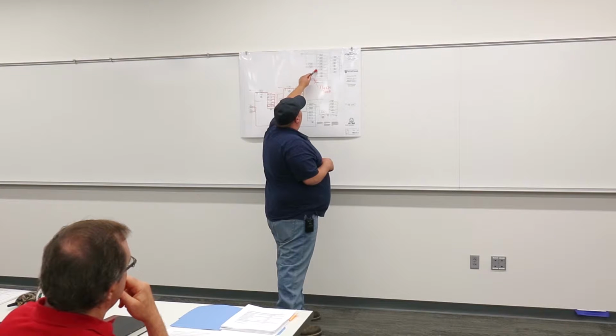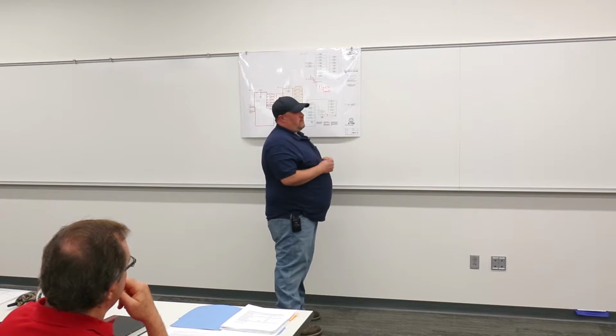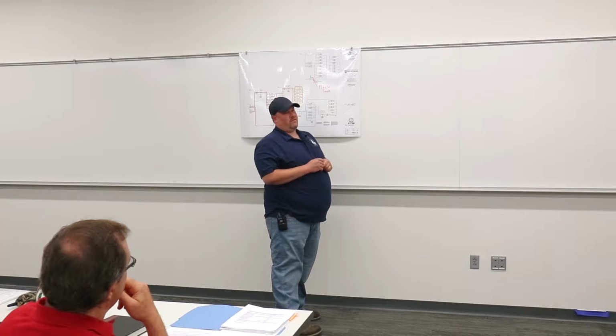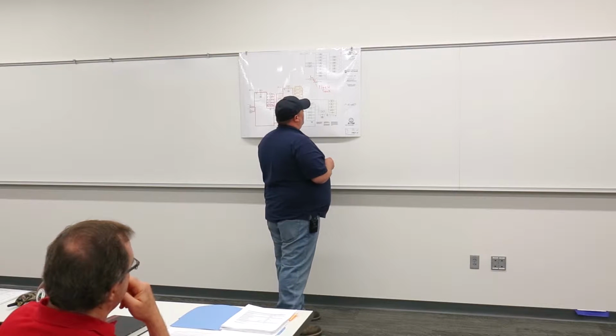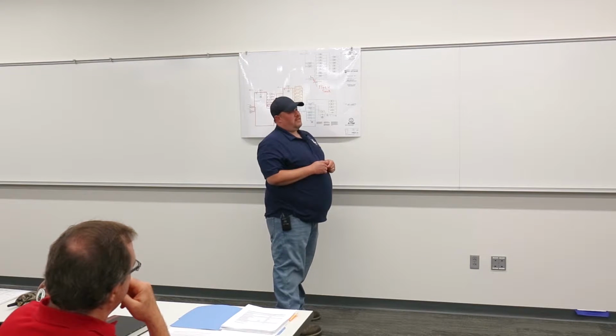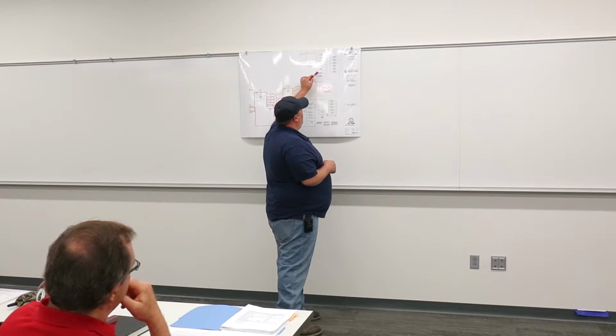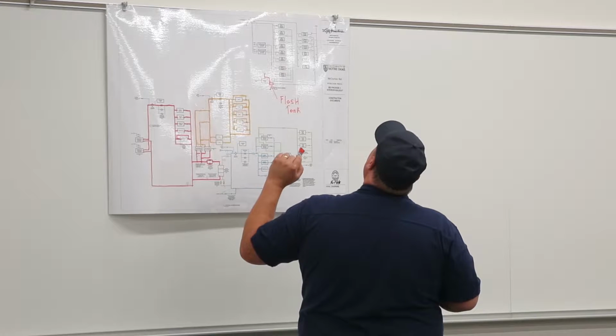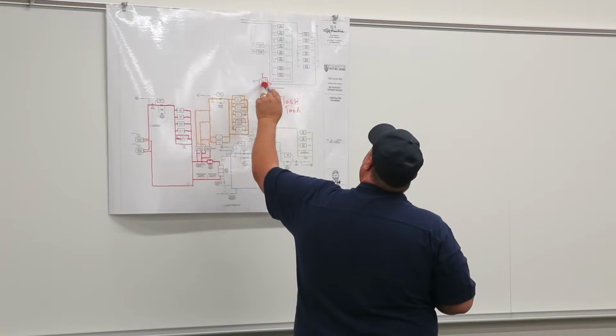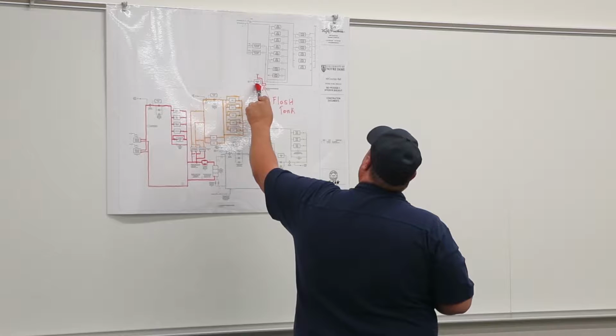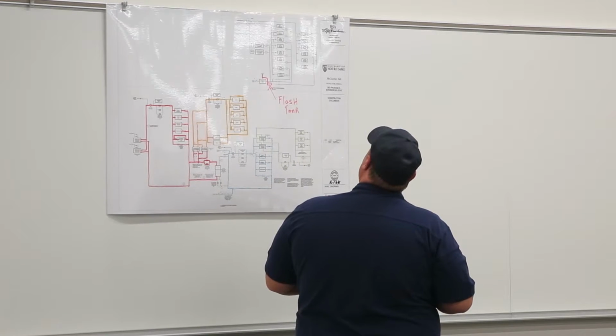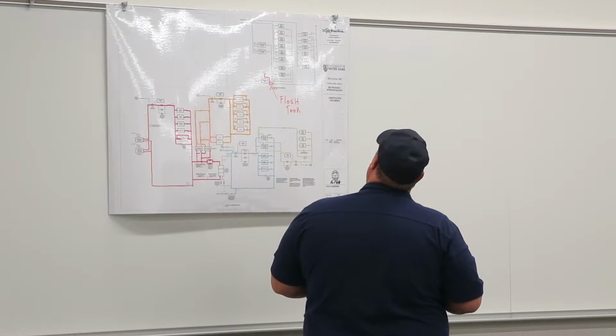I take that back. The way this is drawn in is a little funny, but the low pressure steam does go through and feed our domestic hot water heaters in the heat exchangers in the basement that are just mainly to try to boost the return in the system. We're trying to use the hot water feed from campus, and this is just kind of a supplement before it returns back. Everything ties into one central condensate receiver pump in the basement and gets pumped out with a 3-inch condensate line back out to campus.